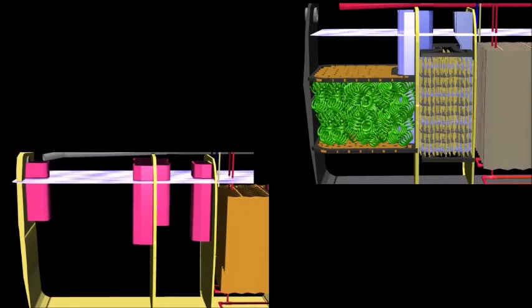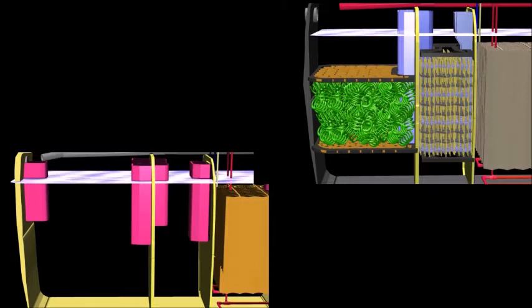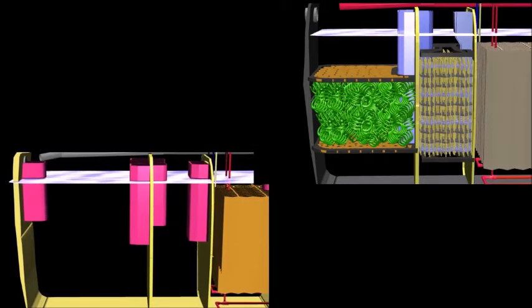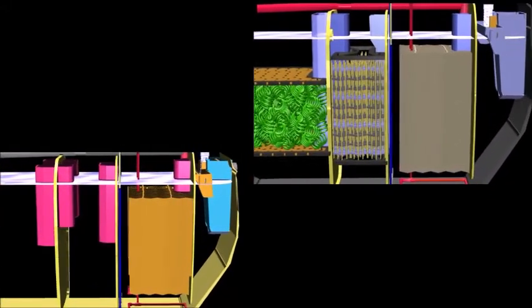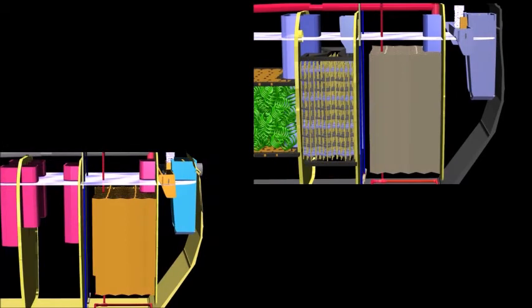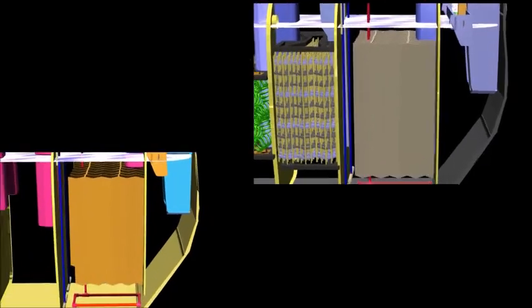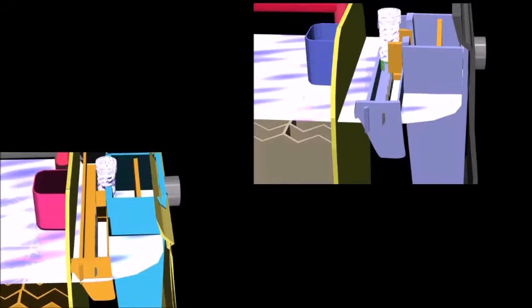At the first step, the treatment using an anaerobic filter tank is the anaerobic filter tank contact aeration process, and the treatment using a sedimentation separation tank is the separation contact aeration process. Both treatment methods use a contact aeration tank and a sedimentation tank for secondary treatment, and the treated wastewater is finally disinfected in a disinfection tank.